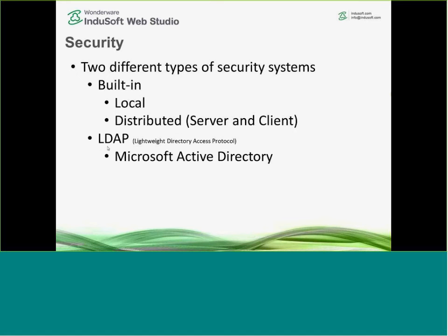Also, there's LDAP, which stands for Lightweight Directory Access Protocol, and most of you will know this as being able to connect using Microsoft Active Directory. So if you've got, for example, a Windows-based PC, and you log in to your domain, well, that's using Microsoft Active Directory. So if you need to use Microsoft Active Directory in a water type application, you don't have to recreate your security system, authenticate against that Microsoft Active Directory, and you don't have to create new users and new groups. So it's another way to do that.